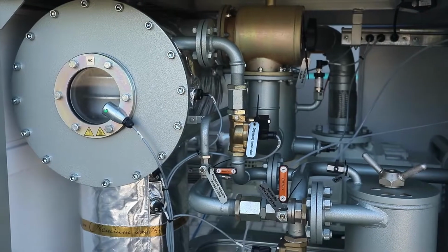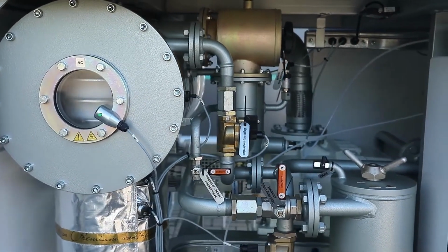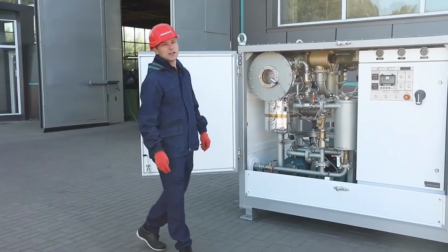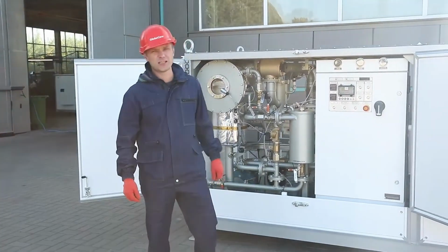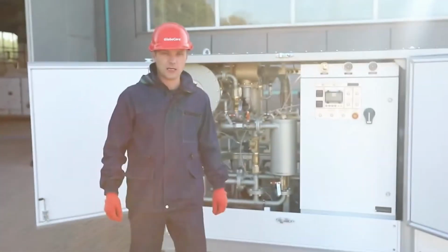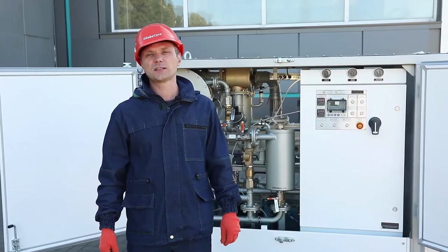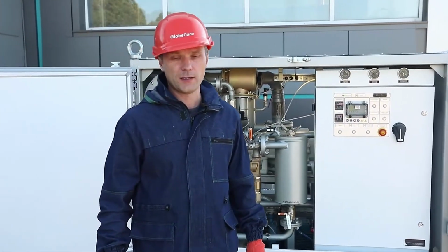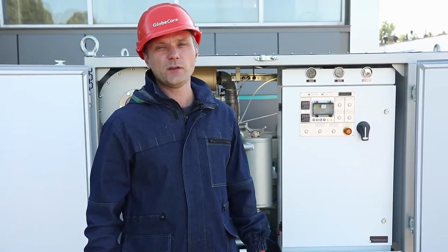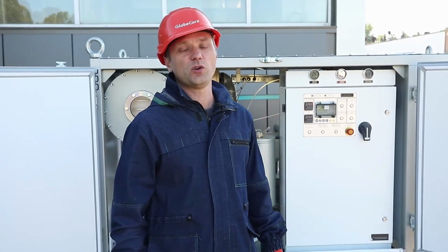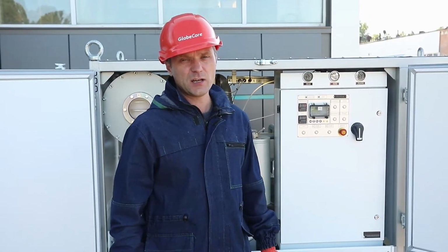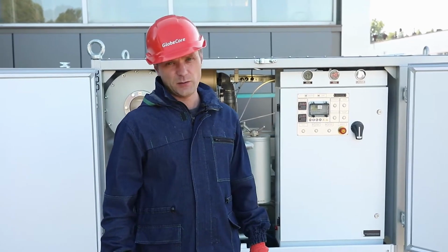After comprehensive purification, the breakdown voltage of insulating oil is not less than 70 kilovolts. The gas content by volume is not more than 0.1%, and the moisture content by weight is not more than 10 grams per ton. In heating and filtration mode, the unit operates with the maximum capacity of 7 cubic meters per hour.